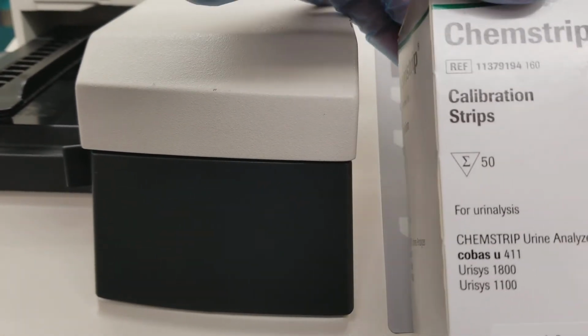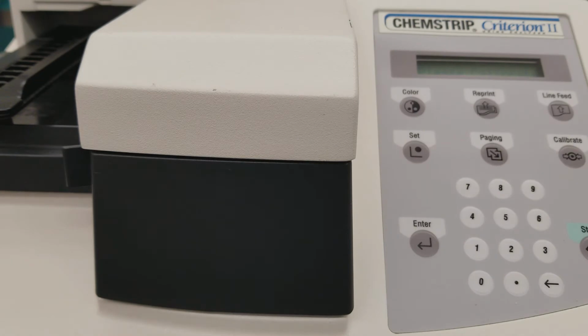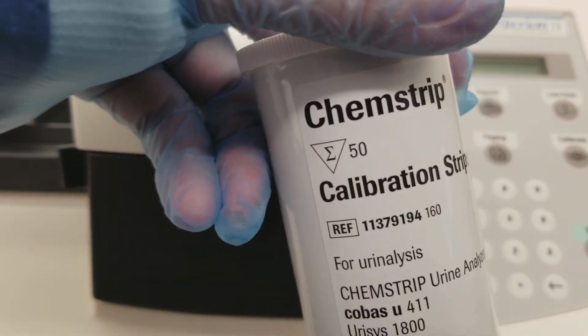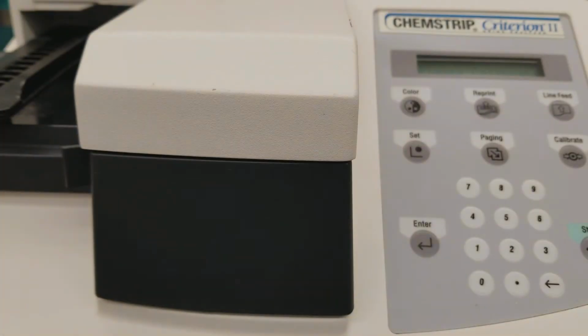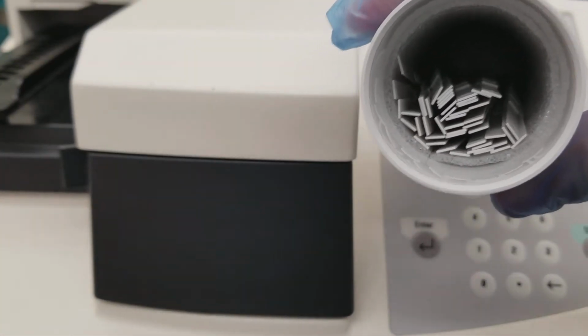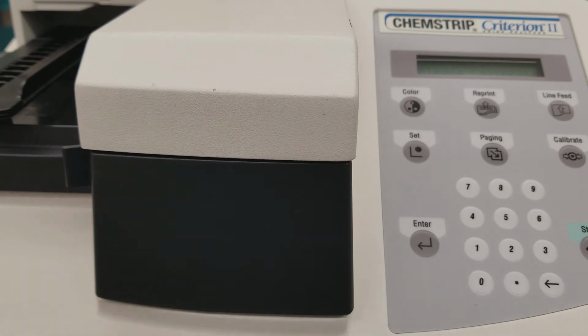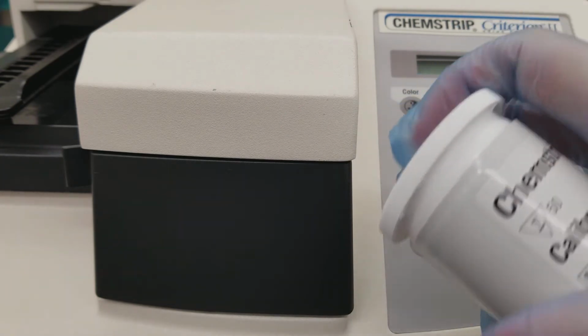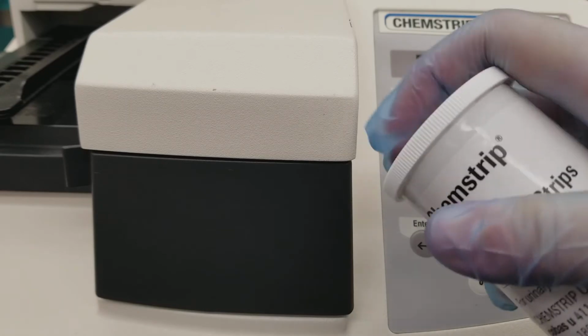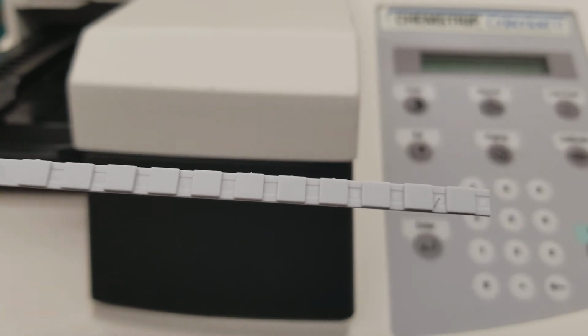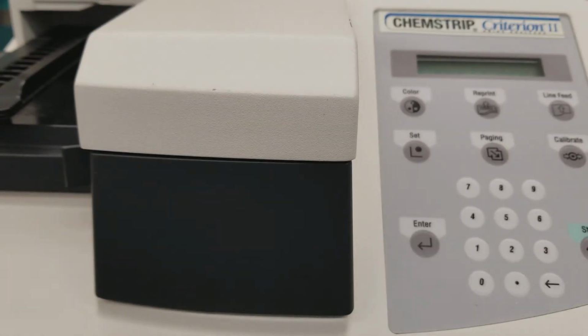I'm going to take the calibration strips here. Make sure they have been closed tightly since the last time, and that they're not expired. These ones obviously are going to be expired. We tend to use a lot of expired things in here, but notice there's strips in there. You want to pull one out, and they look like this. They look like they have no color. Immediately, you're going to want to put that cap back on and make sure it's completely in place. These strips are affected by light as well as moisture, so they can cause false results.